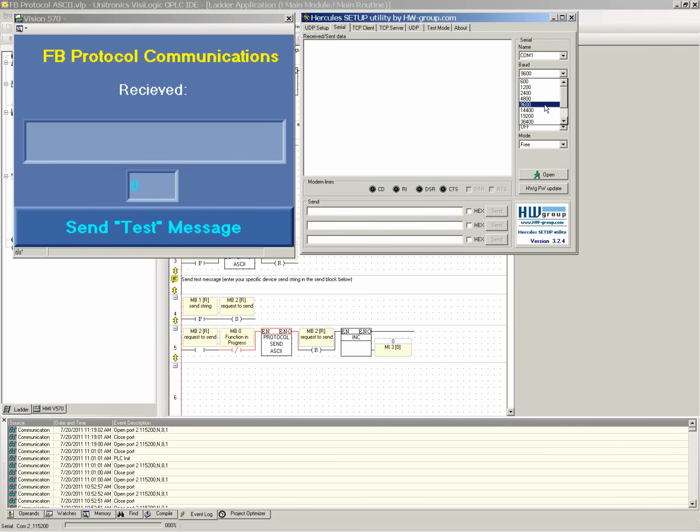The characters won't make sense. They'll be strange uppercase, lowercase symbols. That's one indication when you're trying to troubleshoot. If you don't have the proper baud rate, the message won't make sense, essentially. So what you need to do, main point, is set the correct baud rate.